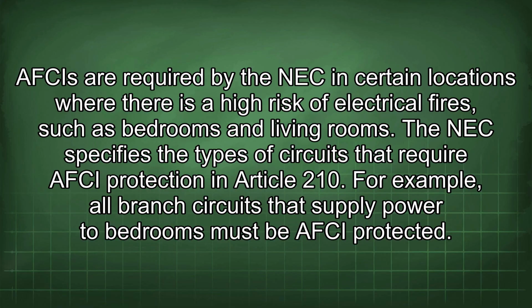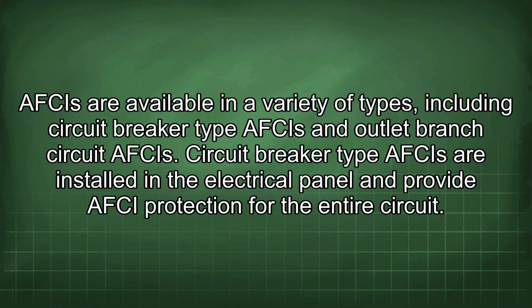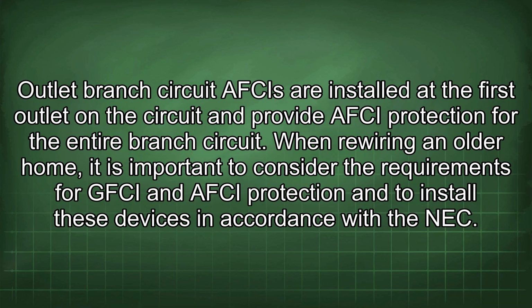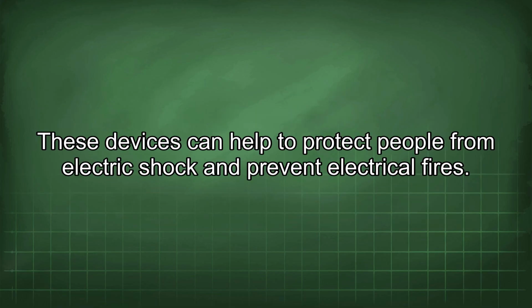For example, all branch circuits that supply power to bedrooms must be AFCI protected. AFCIs are available in a variety of types, including circuit breaker type AFCIs and outlet branch circuit AFCIs. Circuit breaker type AFCIs are installed in the electrical panel and provide AFCI protection for the entire circuit. Outlet branch circuit AFCIs are installed at the first outlet on the circuit and provide AFCI protection for the entire branch circuit. When rewiring an older home, it is important to consider the requirements for GFCI and AFCI protection and to install these devices in accordance with the NEC. These devices can help to protect people from electric shock and prevent electrical fires.